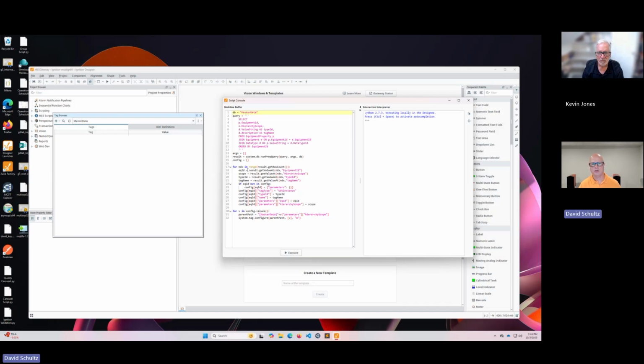I execute that script, and then I go through that result and parse the data, assigning my equipment ID, my scope, my type ID, and tag name. You asked earlier about the UDT name. Yes, that would be that type ID. But when I instantiate it, I'm going to call it something different. That's one of the values that was in the equipment property itself. And then I'm really just creating the instance of that UDT. I'm here at the very last part, and if this is working, we're now going to execute.